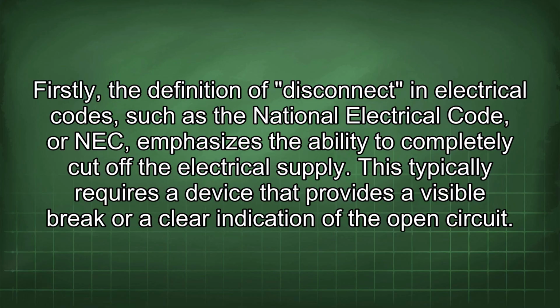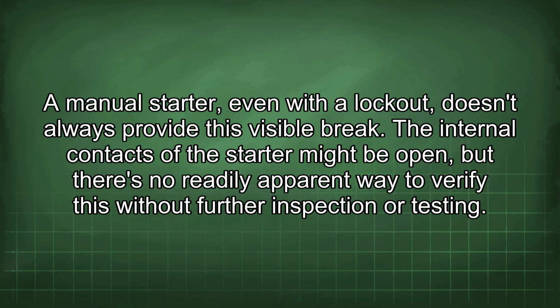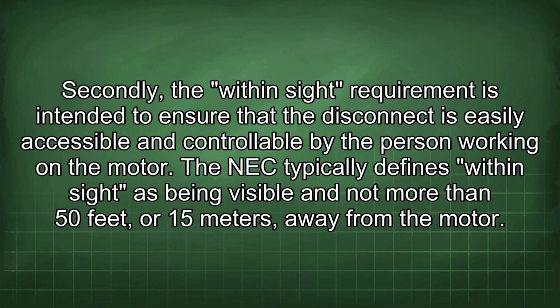the ability to completely cut off the electrical supply. This typically requires a device that provides a visible break or a clear indication of the open circuit. A manual starter, even with a lockout, doesn't always provide this visible break. The internal contacts of the starter might be open, but there is no readily apparent way to verify this without further inspection or testing.